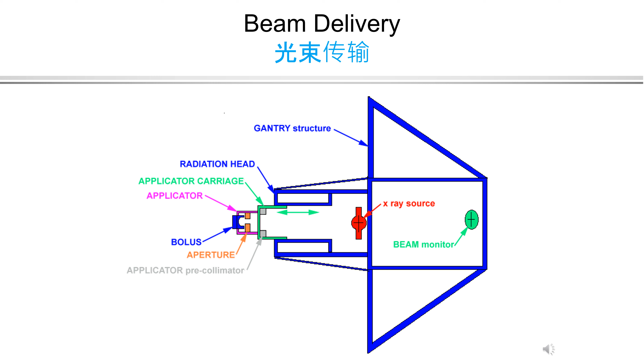During delivery of a treatment, the beam enters the radiation head of the gantry from the right, probably through a bending magnet. Both the position and the focus of the beam can be uncertain. The beam might next pass through a segmented ionization chamber that is used for monitoring and centering the beam. The position of this ion chamber has some uncertainty. Next in this beam line is an X-ray tube used for localization and aligning the patient with the beam. This tube slides into and out of the beam path and its position is uncertain.